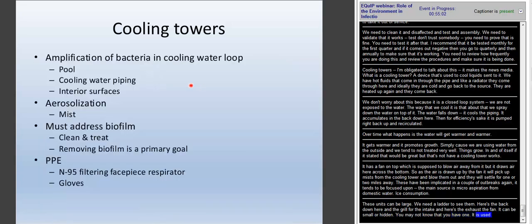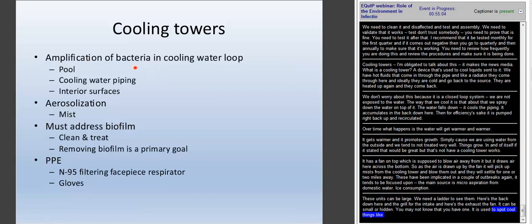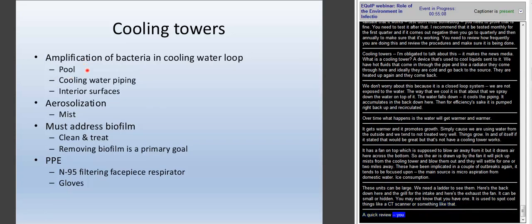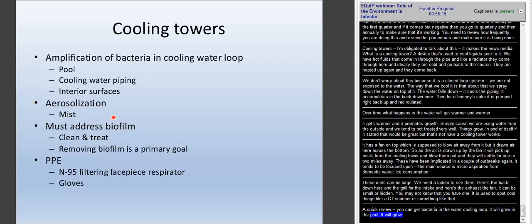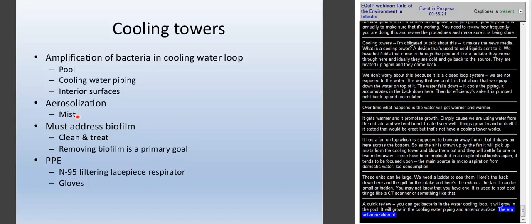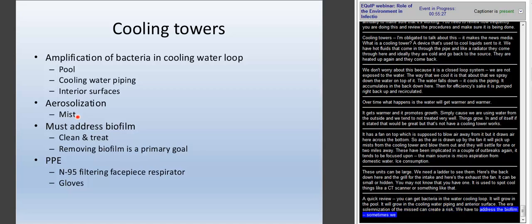So again, quick review: you can get amplification of the bacteria in the water cooling loop. It'll grow in the pool, it could grow in the cooling water piping, and it can grow on interior surfaces. The aerosolization of the mist, if it contains Legionella, does create a risk, but we have to address the biofilm. Sometimes we think if you just kill the Legionella—but you have to destroy the environment that it lives in. If we don't do that, the Legionella will persist. So removing the biofilm is a primary goal.